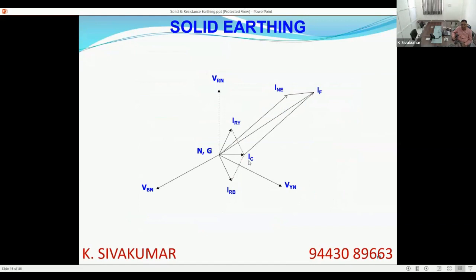Apart from this capacitive current, if it were an ungrounded system, only this current would be the fault current. But since we are solidly grounding, there is another, very big component. Huge fault current will be there, and a reactive component will be there. This major fault current and this negligible capacitive current will vectorially add to give you the effective fault current. Many times this capacitive current is almost negligible compared to the fault current, but for academic interest I have drawn this vector diagram. So the fault current will be the vector sum of the fault current through the grounded neutral and the capacitive discharge currents. But the current is very huge.